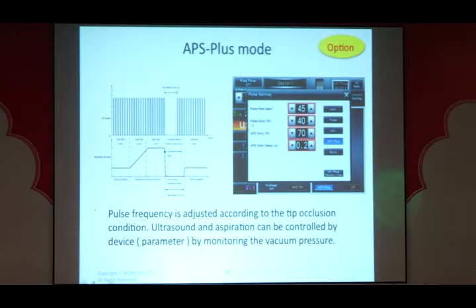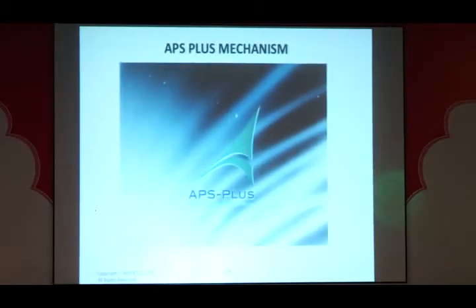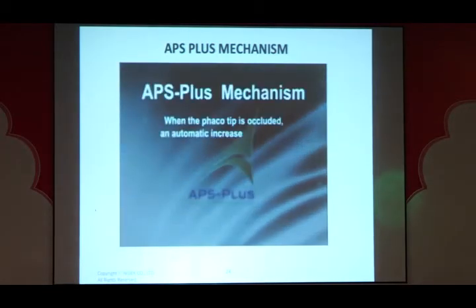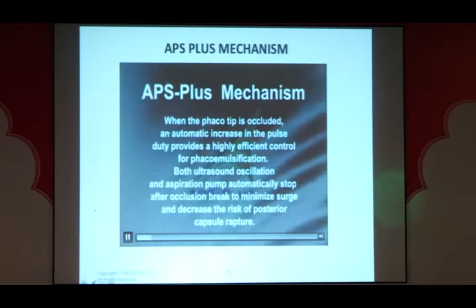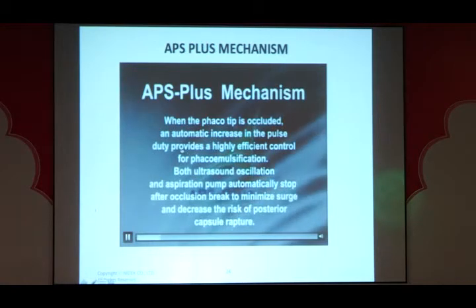But the APS Plus mode has brought in some innovations which I thought somebody should have thought of earlier. Those are things which really have done some wonders, where the pulse frequency is being adjusted after the tip occlusion, and after the occlusion is released, the ultrasound and aspiration are controlled in a way that you get no risk of surge and therefore of causing damage to the posterior capsule. So let's look at the advantages of the technique that is being offered. The APS Plus system is essentially giving you that when the phaco tip is occluded, there is an automatic increase in the pulse rate and therefore pulse duty, which provides a very good control for phacoemulsification.